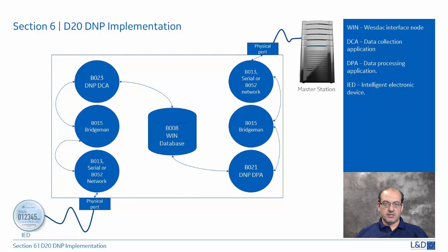The remote terminal unit has the application architecture that will allow the storage of information until requested by the master station. Okay, so let's start the journey of information or data through the DNP protocol from the IED all the way to the master.